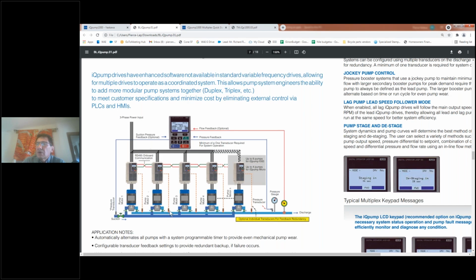So notice that the system properly has pressure sensors going to each of the drives. What this allows us to do is to designate any drive as the master, and in doing so, gives us maximum flexibility. So now we get an additional benefit coming out of this. We eliminate the single point failure of one of the master drive failing, because if the master drive fails in the multiplex system properly designed, and bear in mind this is not just Yaskawa, but anybody's multiplex system, then the second drive in line will assume command. And if that drive fails, the 3rd drive in line will assume command, etc. Because each drive has pressure feedback, it can be the master regulator, and it can call in the other drives as necessary, in the case of one drive failing, the remaining drives. So that's the added benefit.